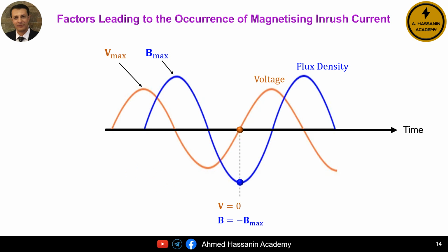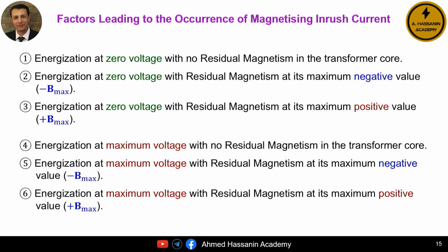We emphasize once again that there is a phase angle of 90 degrees between the voltage and the magnetic flux density under normal operating conditions. This is the case in normal operation only. However, in the transient condition, we find that the phase angle is random, with no specific value. In general, there are 6 conditions or factors that can lead to the occurrence of magnetizing inrush current. 1. Energizing when the voltage is 0 and there is no residual magnetism in the iron core. 2. Energizing when the voltage is 0 and there is residual magnetism in the iron core at its maximum negative value.